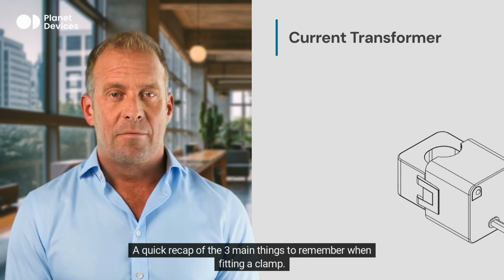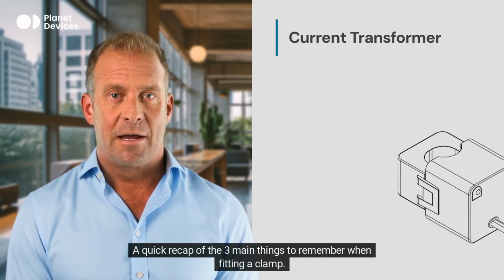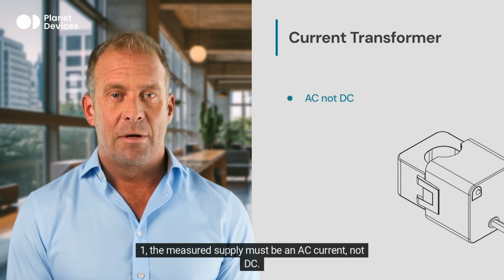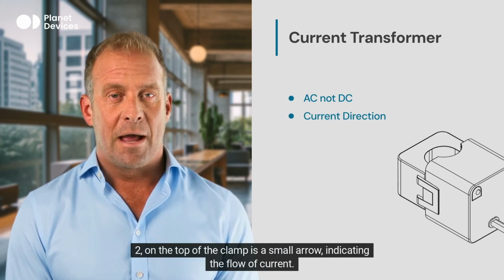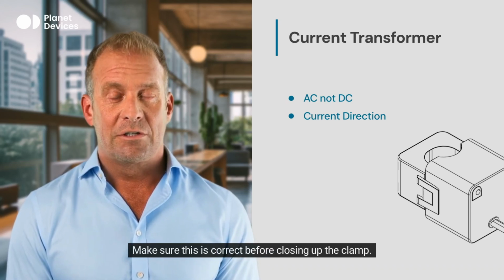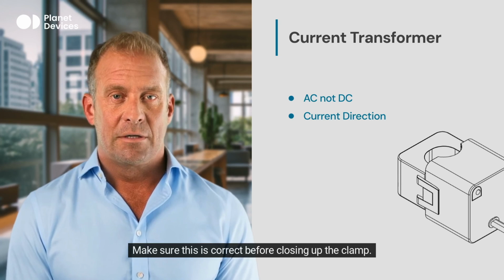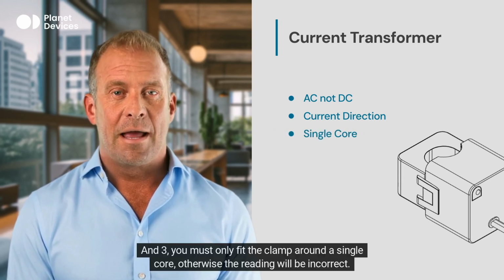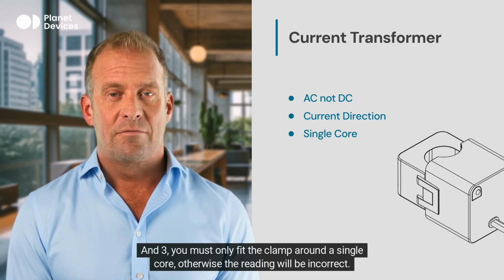A quick recap of the 3 main things to remember when fitting a clamp. 1. The measured supply must be an AC current, not DC. 2. On the top of the clamp is a small arrow indicating the flow of current. Make sure this is correct before closing up the clamp. And 3. You must only fit the clamp around a single core, otherwise the reading will be incorrect.